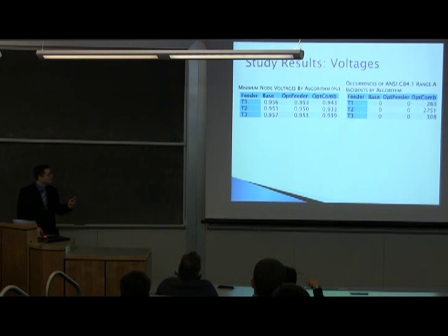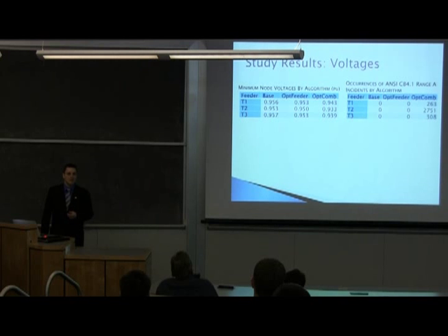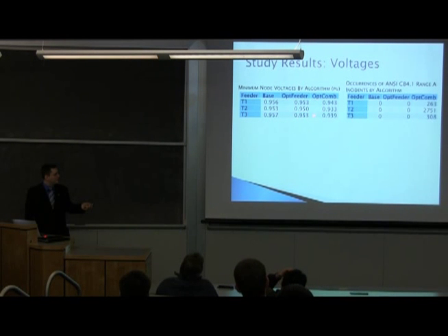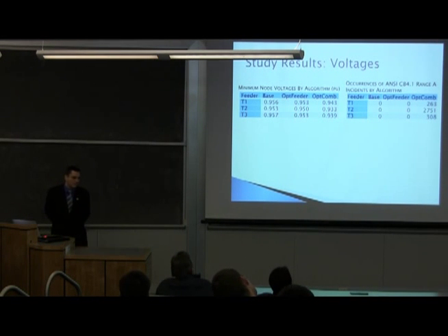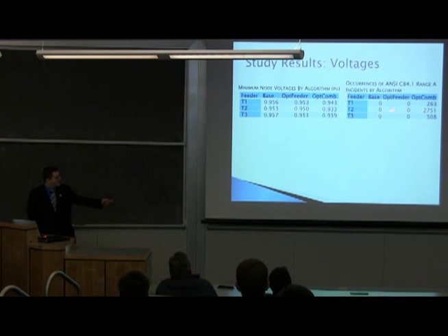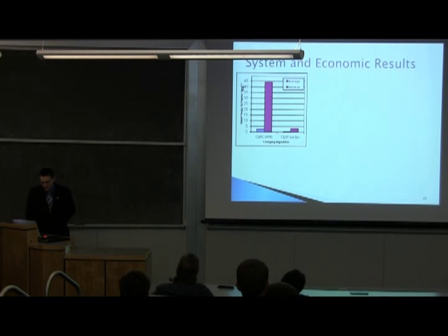Looking at voltages, the ANSI standard says your voltage must be at 0.95 or higher 95% of the time, and if you go lower than that, you're in trouble. The base case stayed above it. The opt-feeder algorithm also stayed above it, though barely. But the unconstrained optimization went below it nearly 3,000 times over the 5-month period. So we can see the system impacts.